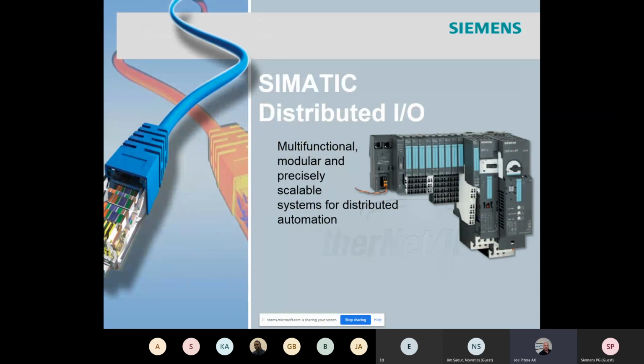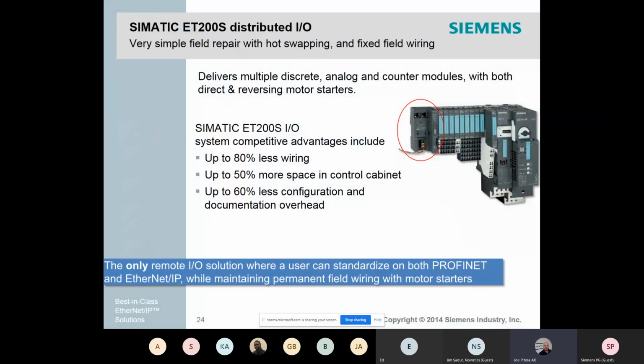This product is unique to the market. With the ability to add starters to the rack, full voltage non-reversing, full voltage reversing soft starters, and its compact footprint and distributed power module, the SIMATIC distributed I/O can be connected to different controllers with both Profinet or Ethernet IP. This benefits in minimum downtime, smaller footprint, and substantial cost reduction in both engineering and commissioning.